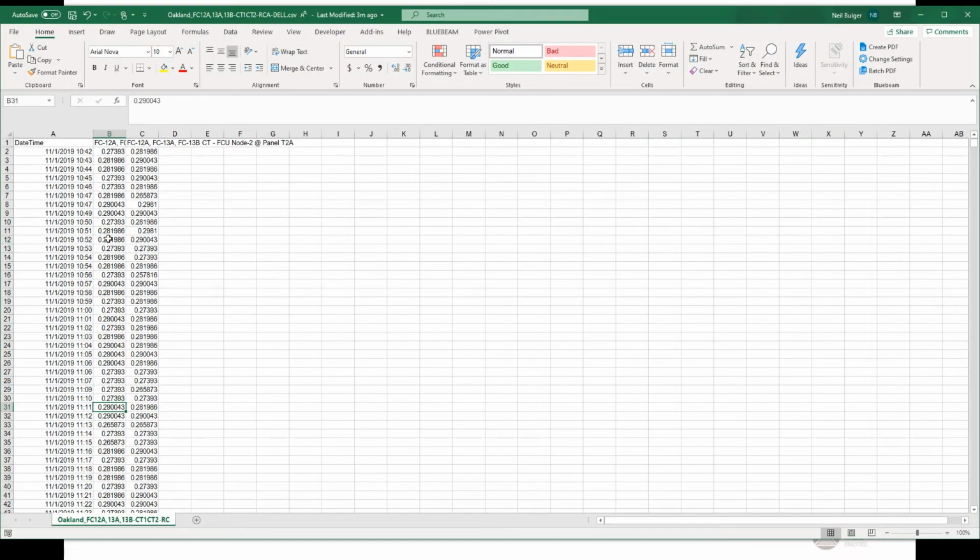I've found that in data, you can have a few types of errors when you start to look at data logs coming from different sources. You can often have blanks where there's literally missing data. Some systems, though it is less common, will fill in blanks with zeros, and we will try to find a sample of that. Generally, that occurs when it's very clear that the reading should not be zero, based on the type of data and the timestamp.